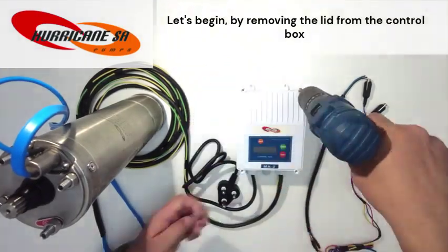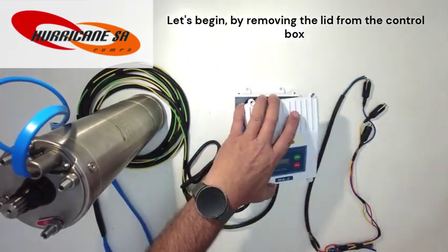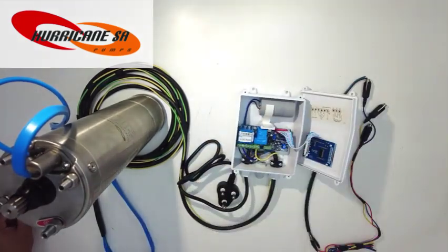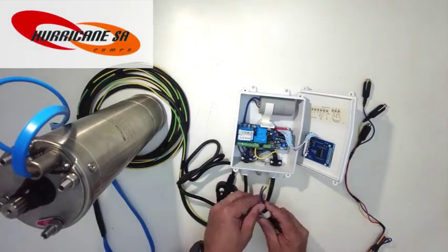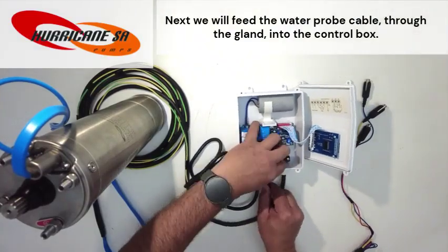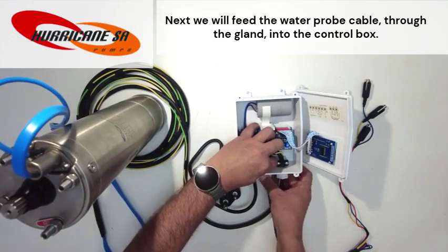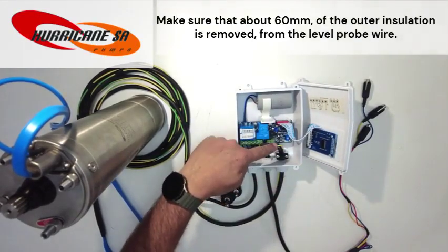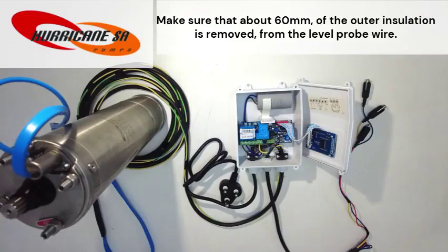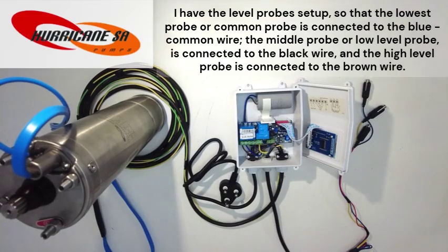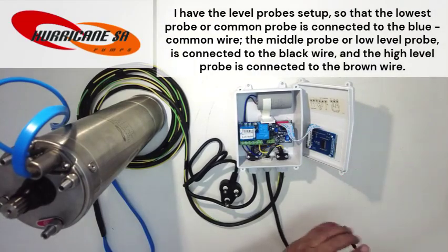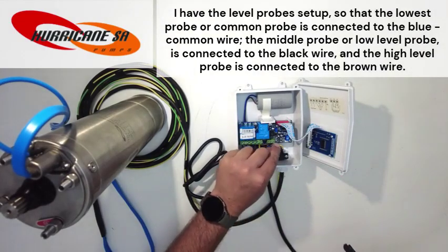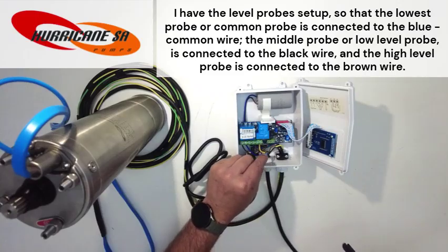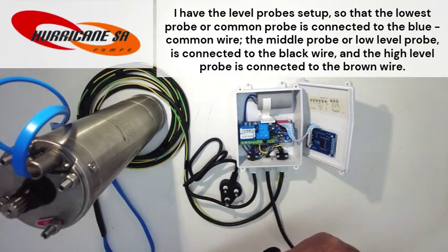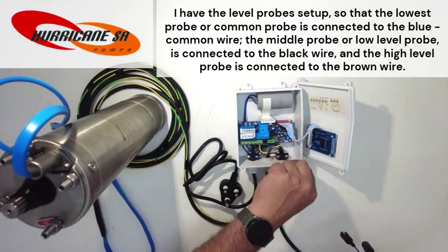Let's begin by removing the lid from the control box. Next, we will feed the water probe cable through the gland into the control box. Make sure that about 60 millimeters of the outer insulation is removed from the level probe wire. I have the level probe set up so that the lowest probe or common probe is connected to the blue common wire. The middle probe or low level probe is connected to black wire, and the high level probe is connected to brown wire.